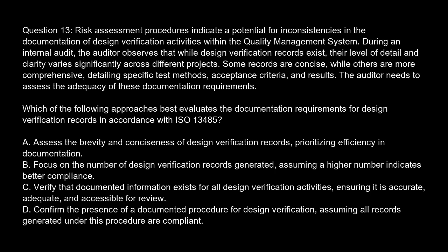Question 13. Risk assessment procedures indicate a potential for inconsistencies in the documentation of design verification activities within the quality management system. During an internal audit, the auditor observes that while design verification records exist, their level of detail and clarity varies significantly across different projects. Some records are concise, while others are more comprehensive, detailing specific test methods, acceptance criteria, results. The auditor needs to assess the adequacy of these documentation requirements.